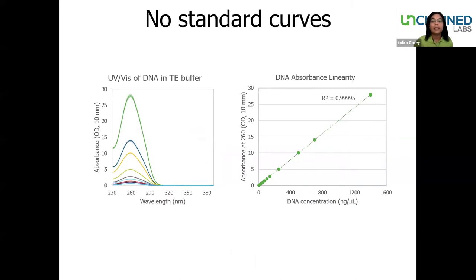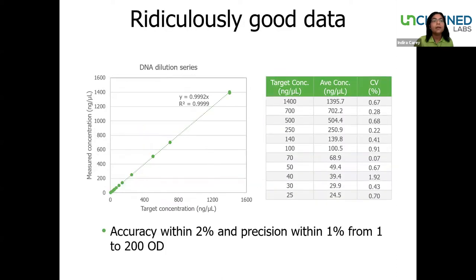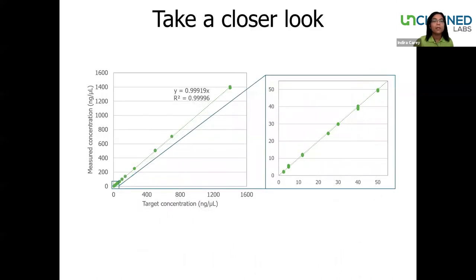Here we're showcasing the linearity and reproducibility of a DNA dilution series, and the R-squared value indicates great correlation. Here's another look at linearity and reproducibility — in this case, a DNA dilution series of calf thymus DNA from 25 nanograms per microliter up to 1,400 nanograms per microliter. Note the low CV values across this dilution range. Zooming in on the lower end of this DNA dilution series really highlights the reproducibility between quadruplicate samples, even at these lower concentrations.